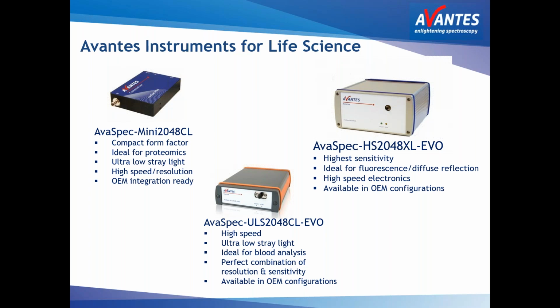And then finally, for more demanding applications, we have the last unit there, the Avantes HS 2048XL EVO. This is one of the most high sensitivity systems that we offer. It uses a 0.22 numerical aperture optical bench to match that of the fiber optic cable. So this makes it great for applications with low light, such as fluorescence and diffuse reflectance applications. And this also features the EVO high-speed electronics. And I'll mention that all three of these systems are available in OEM configurations.